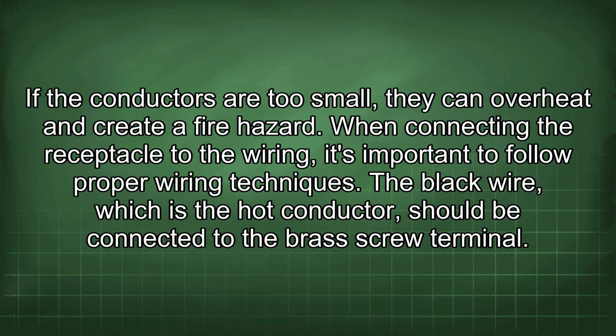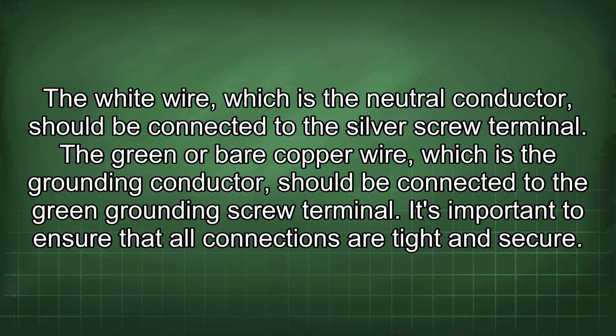The black wire, which is the hot conductor, should be connected to the brass screw terminal. The white wire, which is the neutral conductor, should be connected to the silver screw terminal. The green or bare copper wire, which is the grounding conductor, should be connected to the green grounding screw terminal. It's important to ensure that all connections are tight and secure.